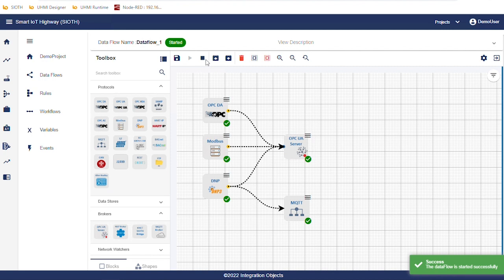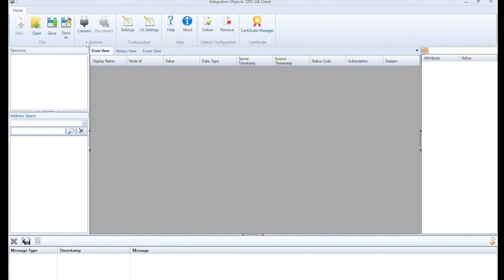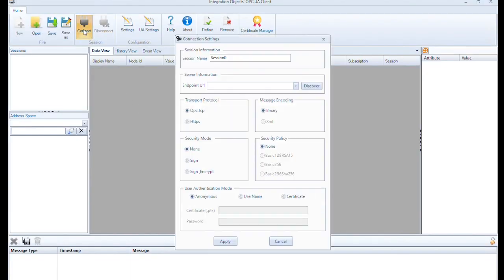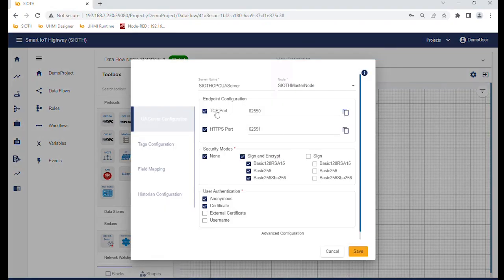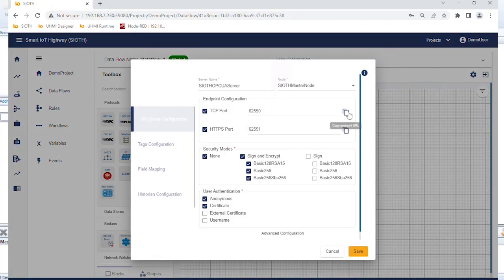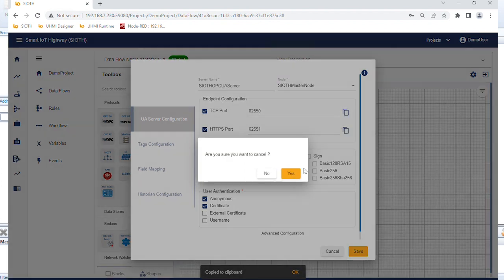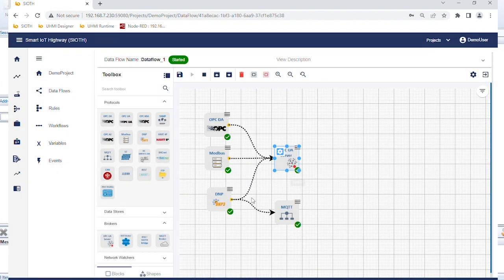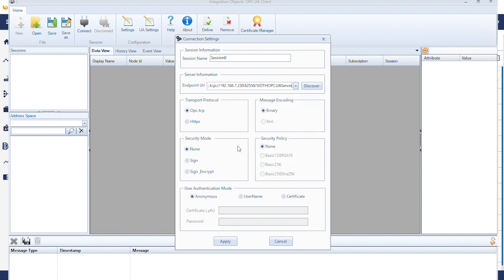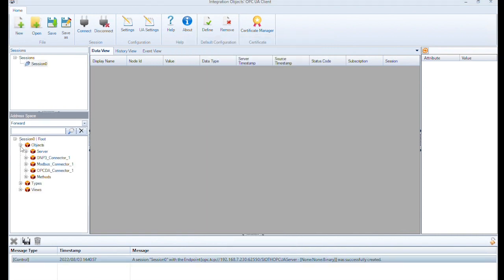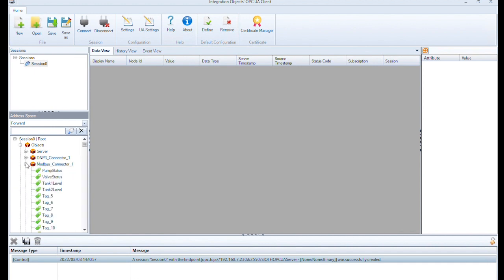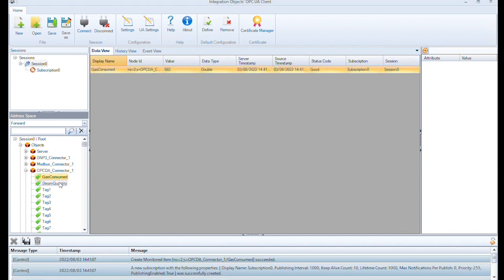To do that, we will use a test OPC UA client. Connect using the SIOTH OPC UA server endpoint. We can copy it directly from the connector then paste it in this field. Once connected, we can browse DNP tags, Modbus tags and OPC DA tags. Drag and drop some tags to display their values in real time.